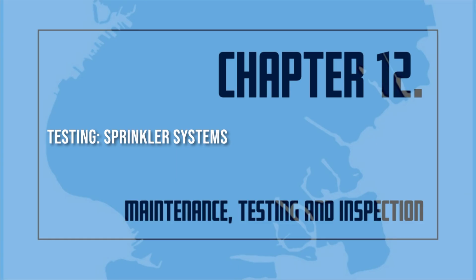Gauges. Gauges shall be replaced every 5 years or tested every 5 years by comparison with a calibrated gauge. Gauges that are not accurate within 3% of the full scale shall be recalibrated or replaced. Sprinklers. Extra high temperature. Representative samples of solder-type sprinklers with a temperature classification of extra high, 325 degrees Fahrenheit or greater, that are exposed to semi-continuous to continuous maximum allowable ambient temperature conditions shall be tested at 5-year intervals.